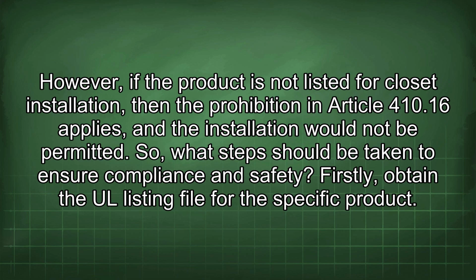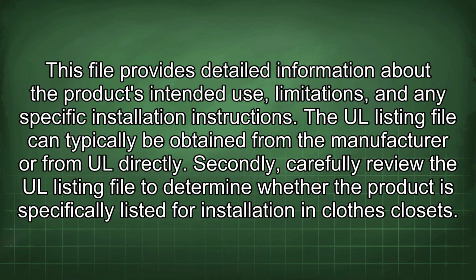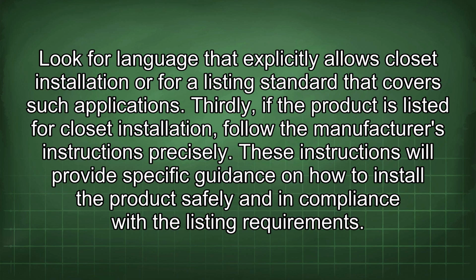Firstly, obtain the UL listing file for the specific product. This file provides detailed information about the product's intended use, limitations, and any specific installation instructions. The UL listing file can typically be obtained from the manufacturer or from UL directly. Secondly, carefully review the UL listing file to determine whether the product is specifically listed for installation in clothes closets. Look for language that explicitly allows closet installation or for a listing standard that covers such applications.